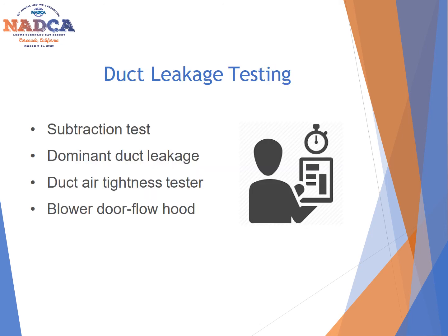Like I mentioned earlier, when you use a blower door, the system is actually set up where there are different tests that you can run, whether they be subtraction tests or just different leak tests that you can run utilizing computer software to help tell you how much leakage you have within the home. Then after you make the repairs, you can go back and run the test again and show the improvements. And that gives you a good way to show the homeowner that you have actually improved their home, or even a facility owner that you've improved the building envelope and tightened it up for them, which will ultimately lead to less duct leakage and lower utility bills.